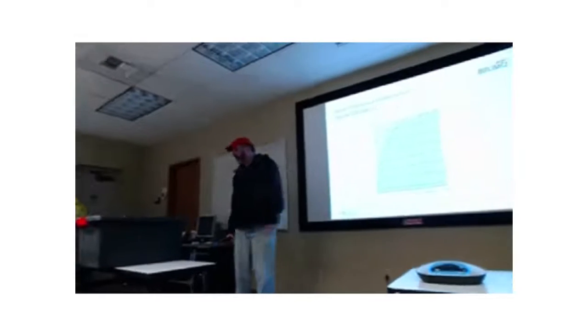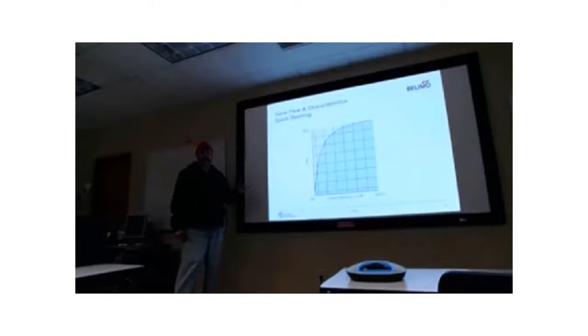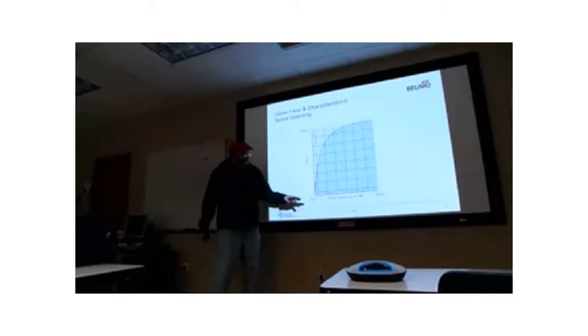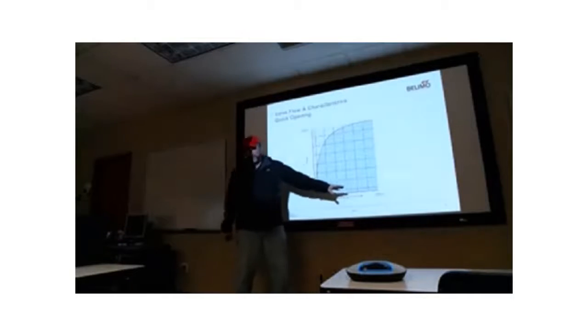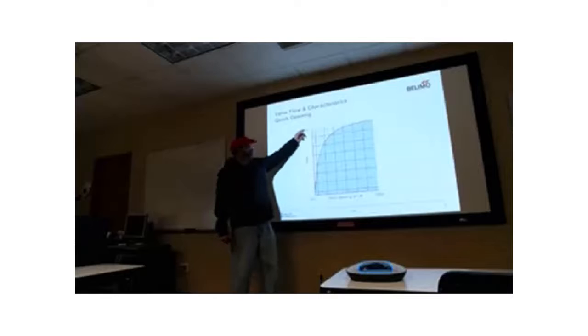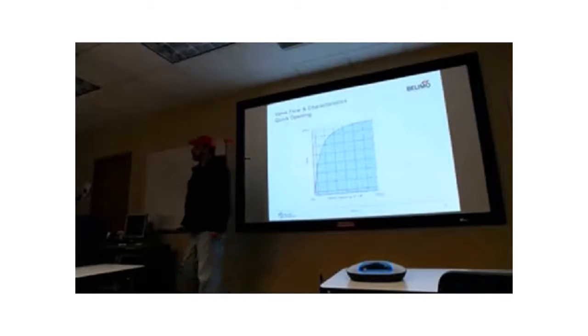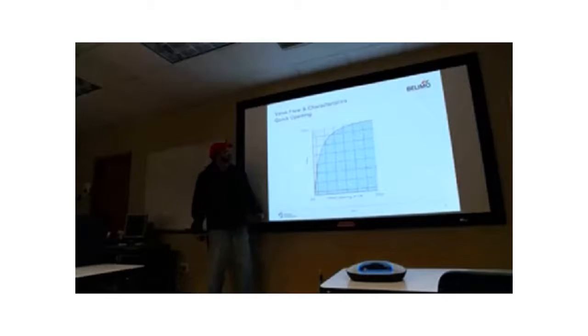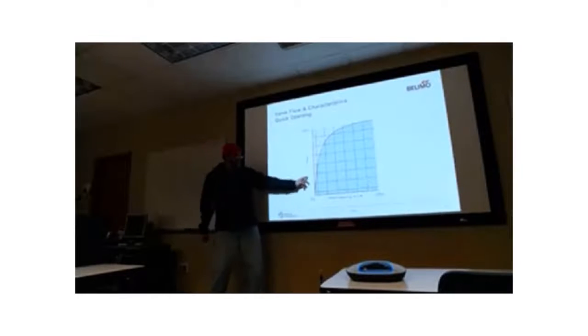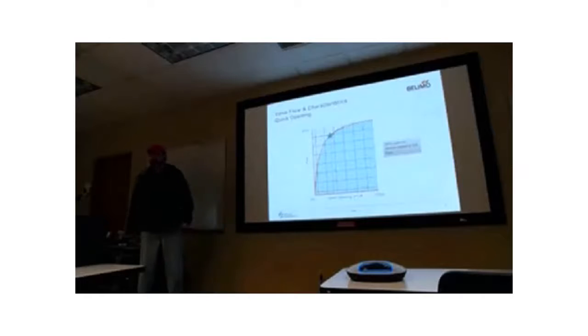So when I talk about valve characteristics, I'm not talking about the way it looks or its color. What I'm talking about is, as you open the valve from 0 to 100%, what does the flow do? What's the flow through the valve? I'm sorry, am I blocking you? Okay. So the first one that we deal with is called quick opening. And if you look at the way that curve goes, you can see why they call it quick opening, right? Because when you start out, if you open that valve maybe 30% open, something like that, you get almost 100% flow real quick. And that's good for some applications, but not so good for others, right?